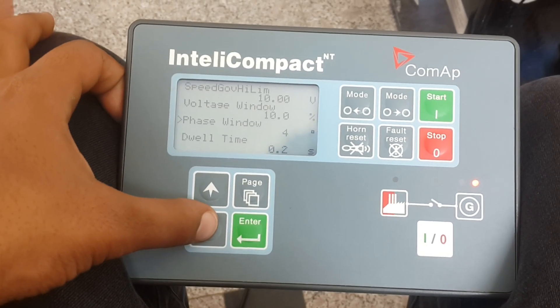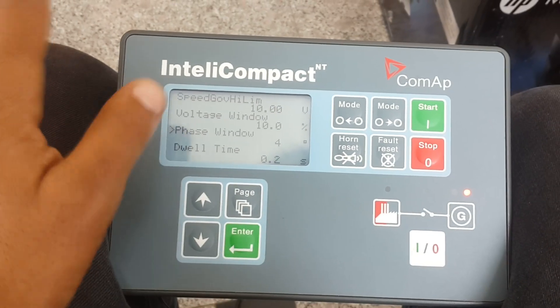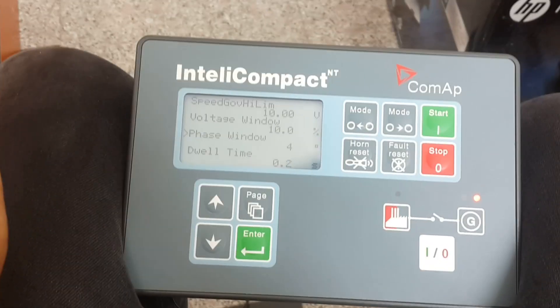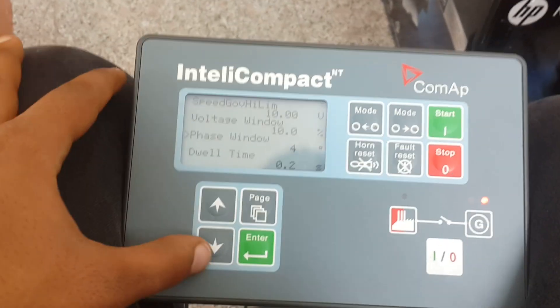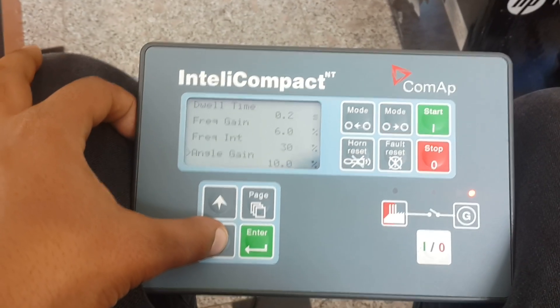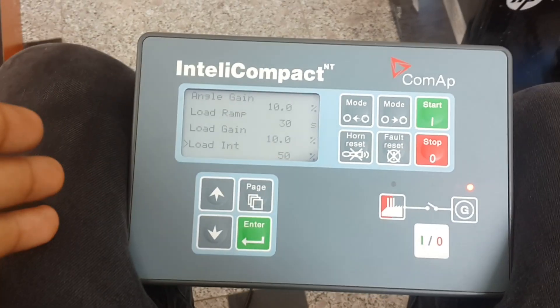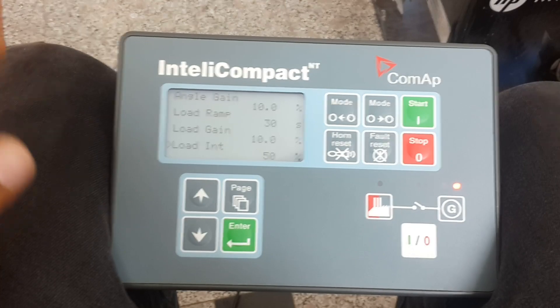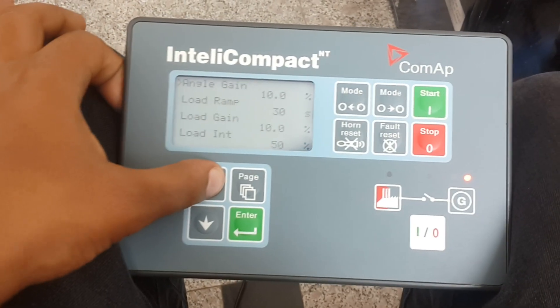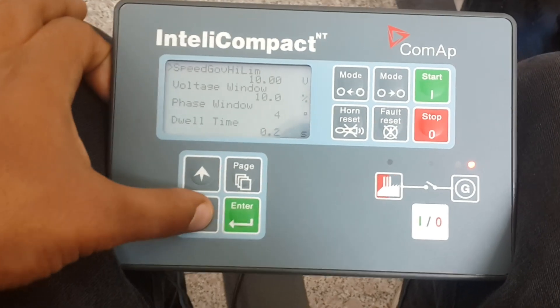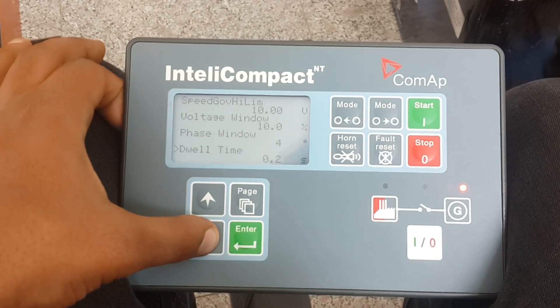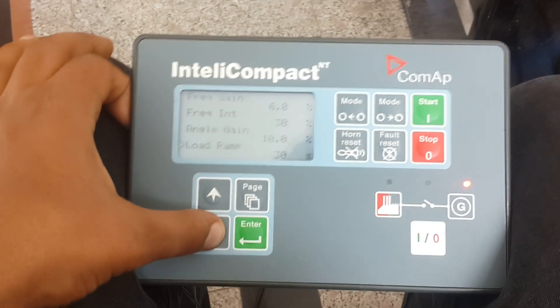The phase window is the degree limit for syncing — it shows four degrees here. If it is beyond four degrees it will not sync; it will just wait for the gen set frequency and voltage to match up. The moment they match up, it will automatically close the breaker. Dwell time, frequency gain, frequency integral, angle gain, load ramping, load gain — these things you can look up online. It's better to do your homework before going into anything.